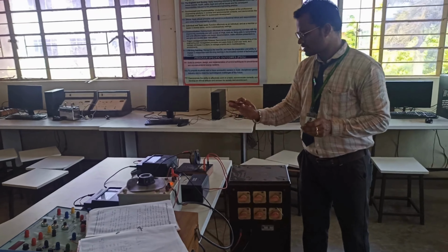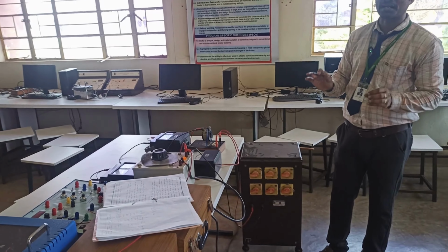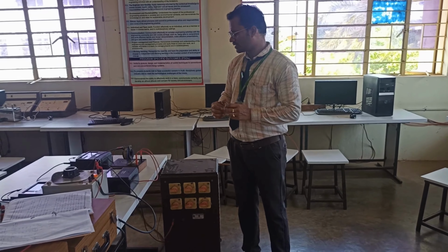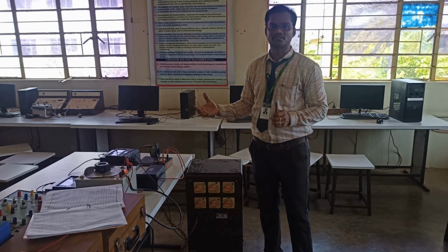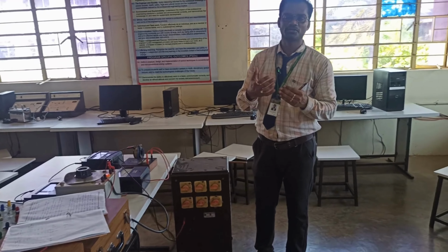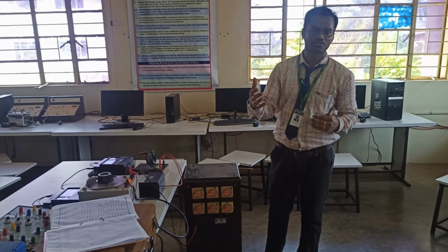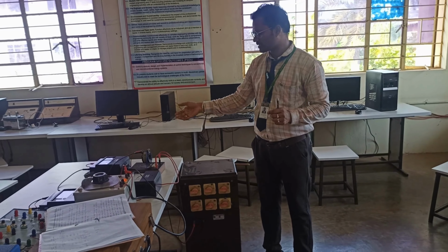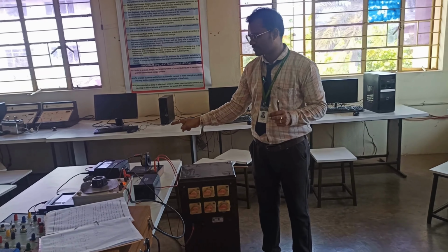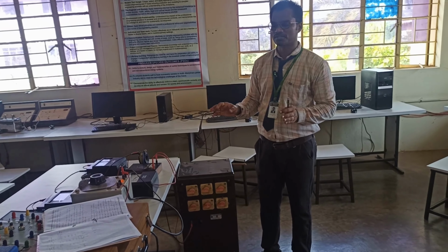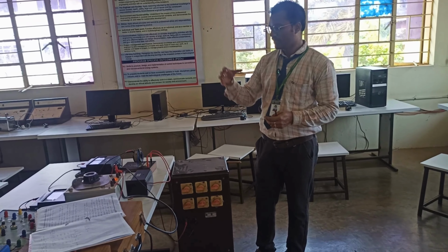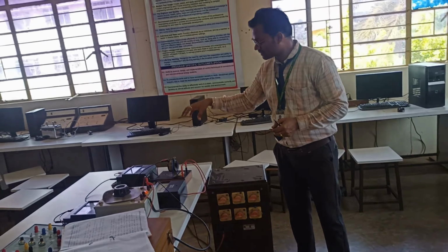So this is the process of how to measure the current on the secondary side by using a current transformer. This is generally used in instrumentation. In substations, where they want to record 200 amperes of current, which is not possible with an ammeter, they downscale it with the help of a current transformer, which you can see is circular in nature. This is the process. So now we have measured the current using a current transformer, and we calculated the error created by this current transformer.